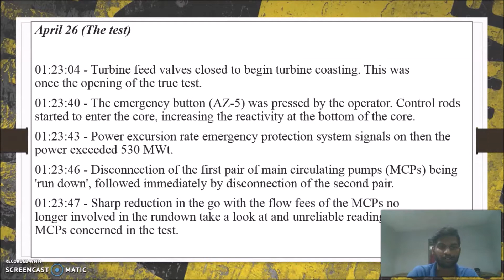And then the disconnection of the first pair of main circulating pumps, the MCPs, was done and they were having a rundown, followed immediately by the disconnection of the second pair of MCPs. And then a sharp reduction in the flow rates of the MCPs was found. At 1:23, the MCPs were no longer involved in the rundown. And at 1:24, the control rods stopped operating. The clutch mechanism's power switch was turned off before they reached the lower limit. The power switch of the clutch mechanisms was also turned off.